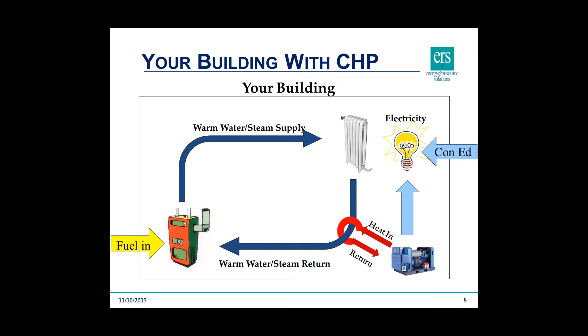So this has a number of advantages. It can provide 24/7 backup power, which we'll go into much more detail on later, but also allow you to purchase much less electricity from the grid. We have a term we call spark spread, the difference in cost per unit gas as compared to per unit electrical power. Typically, gas is much cheaper than electricity, so if you can produce your own power from natural gas, you can save significantly on utility bills. We can see anywhere from a 20% reduction in utility costs with a successful CHP installation, which is pretty incredible.